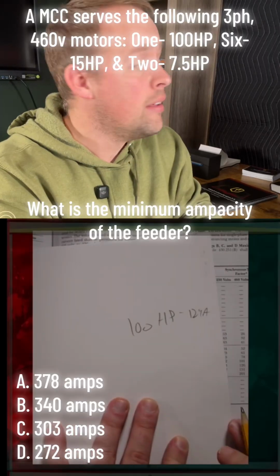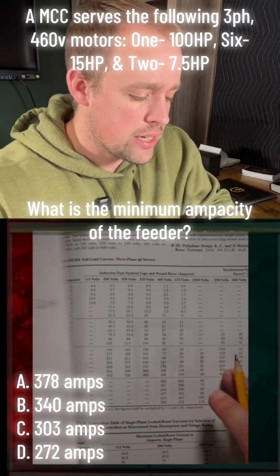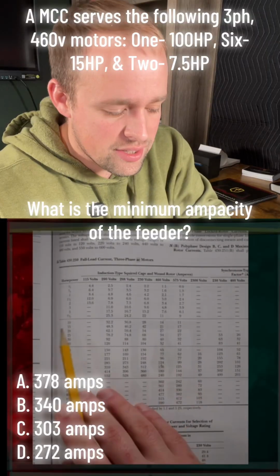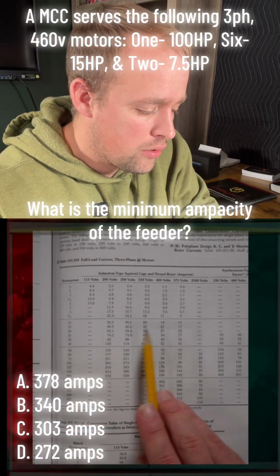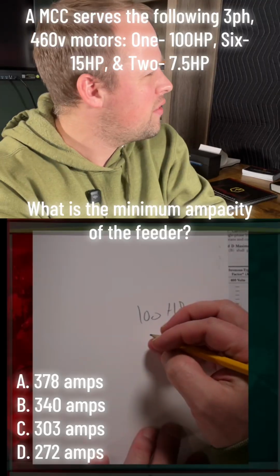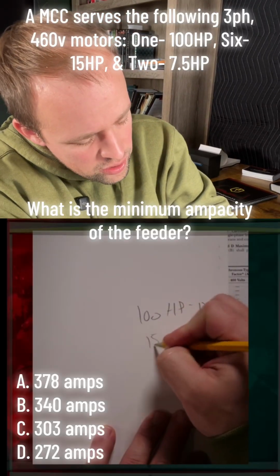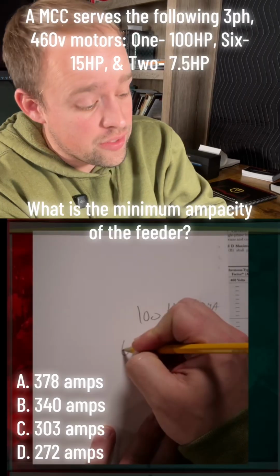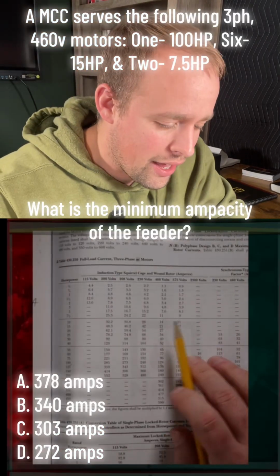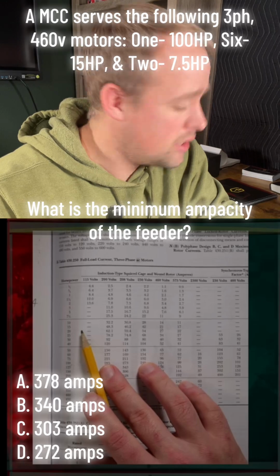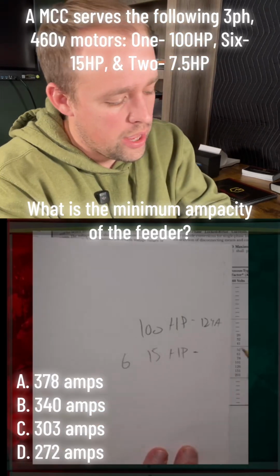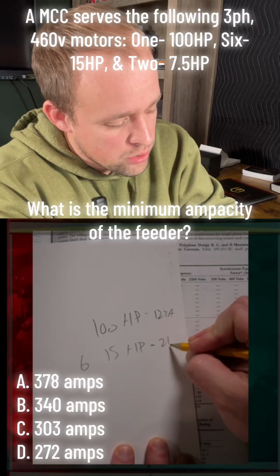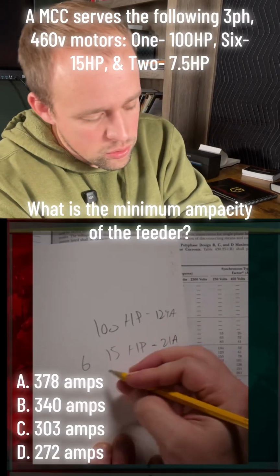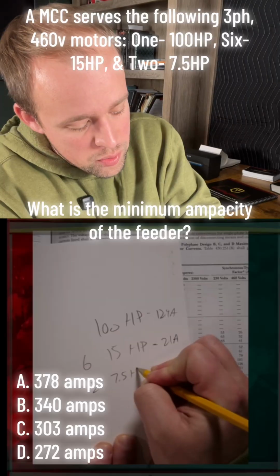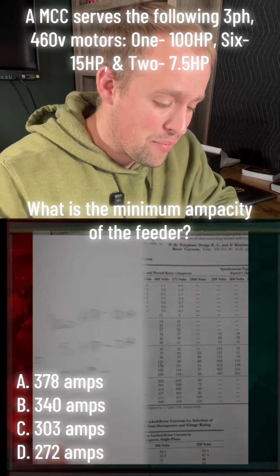Most likely that's going to be my largest motor, but let's continue just in case. We have 6 15 horsepower motors. So that's 21 amps. It's important to write down that there's 6 of them. 15 horsepower, so 21 amps. Sorry if my paper's all over the place. And then we have 2 7.5 horsepower. I'm writing very quickly because I'm running out of time in this video. So 7.5 horsepower at 460 volts is 11 amps.